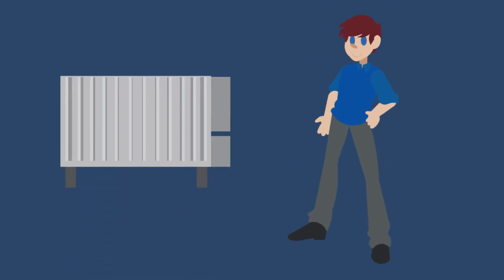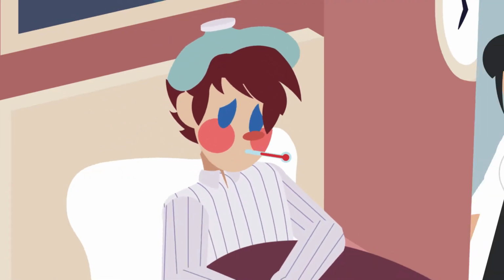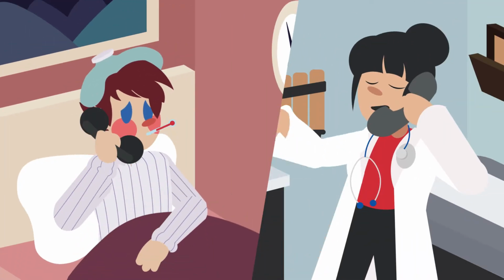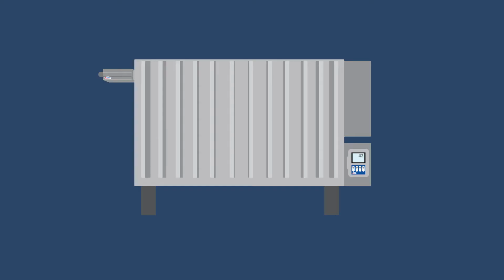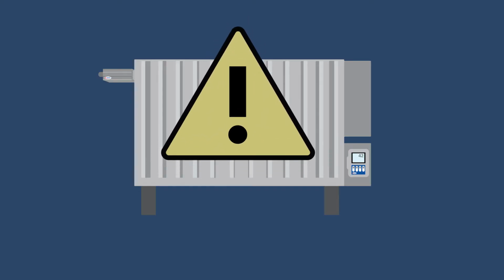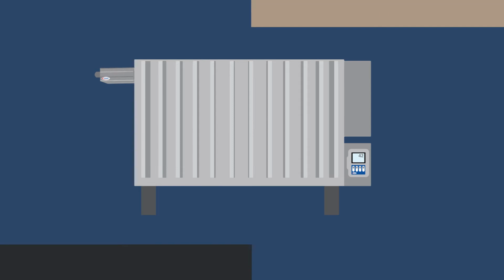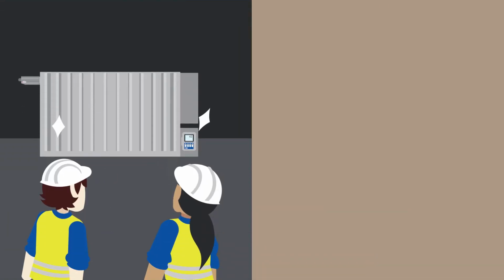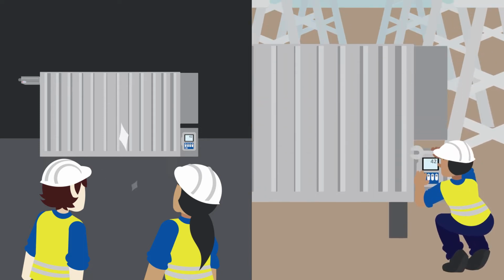Determining the health of a transformer can be compared to assessing the health of a person. However, there is one key difference. Humans can recognize when they're not feeling well and reach out and get attention when needed. Transformers will only be able to ask for attention if they have a monitoring system. Fortunately, monitoring systems are not expensive and can be installed when the transformer is first built or installed after the transformer is in service as a retrofit.